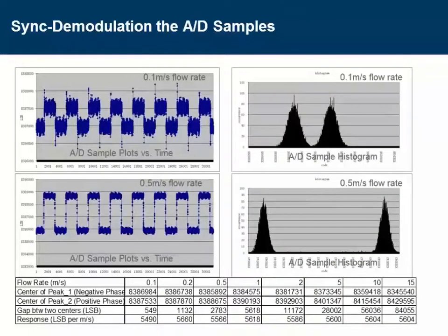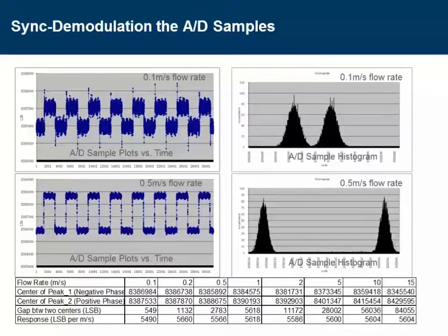The plot here shows an example of how the synchronous demodulation is working for two different flow rates. We can see that the ADC samples are switching up and down — the rectangle waveform versus time is due to the alternating sensor excitation, creating positive phase and negative phase. When making a histogram of this, the ADC samples become two peaks. From the separation of these two peaks, one is able to calculate the flow rate. For example, the peak separation at 0.5 meters per second is about five times the separation at 0.1 meters per second. For the specific gain and sensitivity in this configuration, the flow rate is about 5,600 LSB per meter per second. The response on the range from 0.1 to 15 meters per second is quite linear.